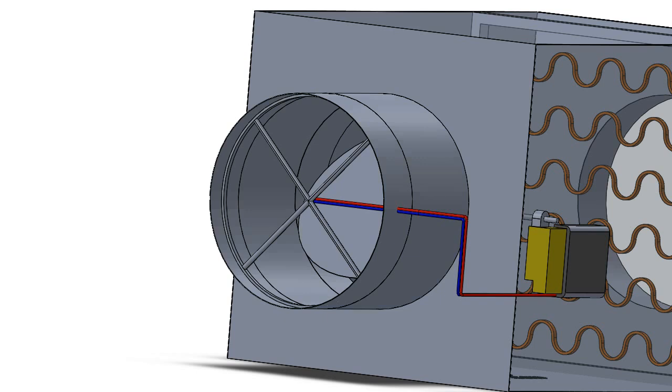But basically, all you need to know about this is there are some small pinholes along the front surface here and also on the back of it. And if you imagine you've got the supply air coming in here and hitting the front of this, then it's going to impact on this and cause a pressure. So it's going to have a high pressure side on the front here. And obviously, on the backside, you're going to get a low pressure point.